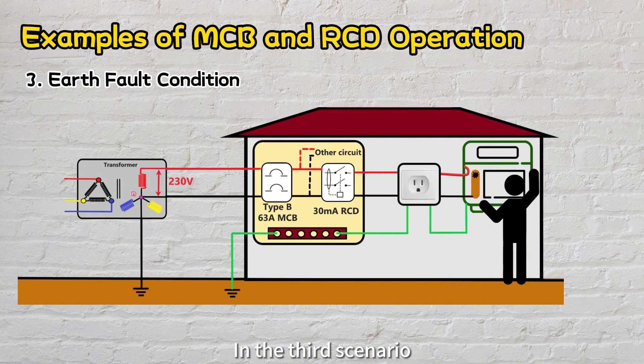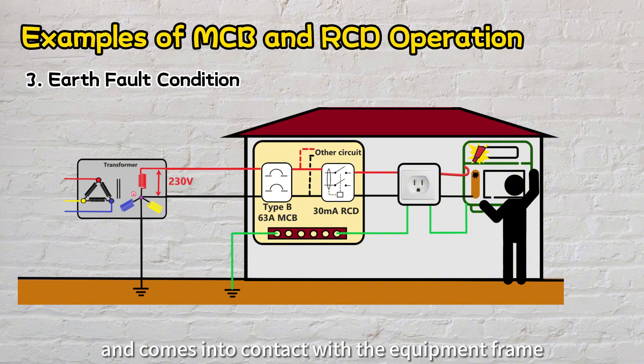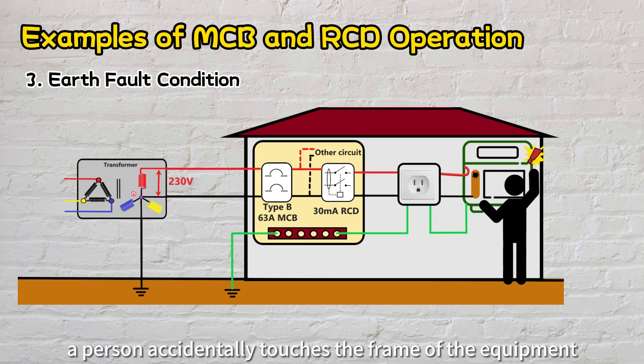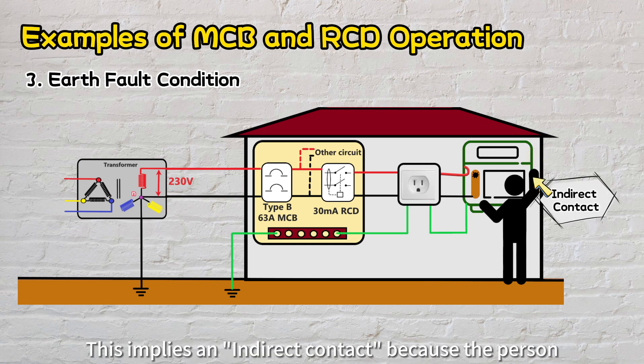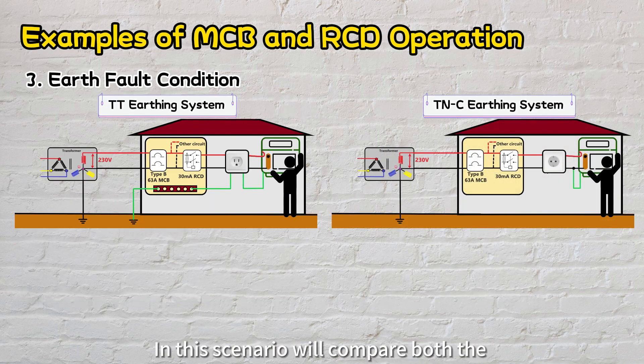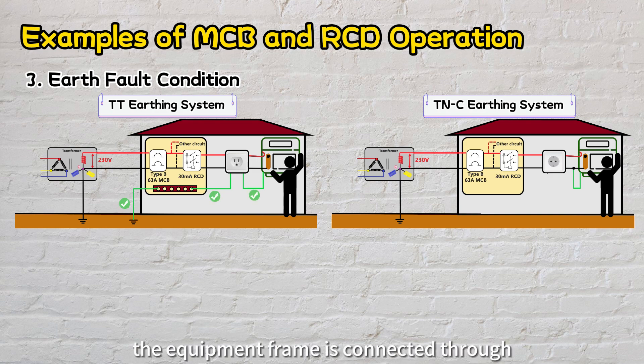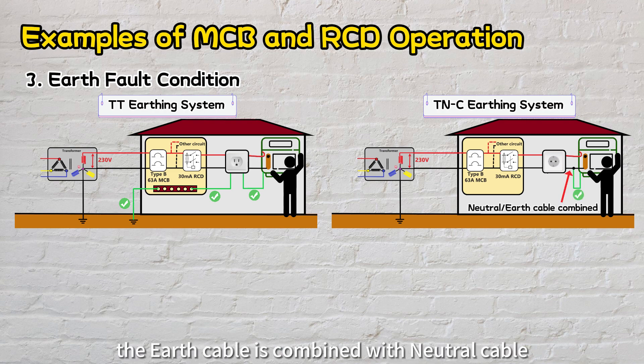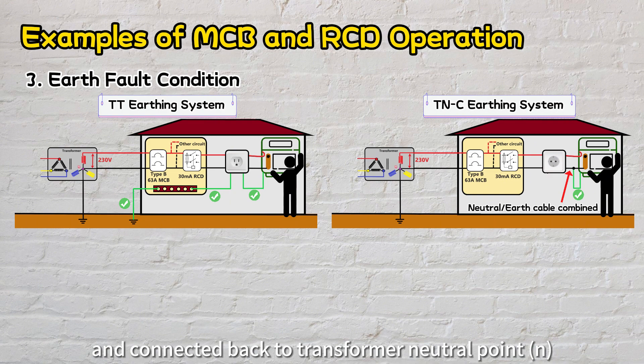In the third scenario, we will examine an earth fault situation where the live cable is broken and comes into contact with the equipment frame. Simultaneously, a person accidentally touches the frame of the equipment — an indirect contact because the person does not directly touch the live cable. In this scenario, we'll compare both the TT and TNC earthing systems. For a TT system, the equipment frame is connected through an earth cable to an earth rod. For a TNC system, the earth cable is combined with the neutral cable and connected back to the transformer neutral point.